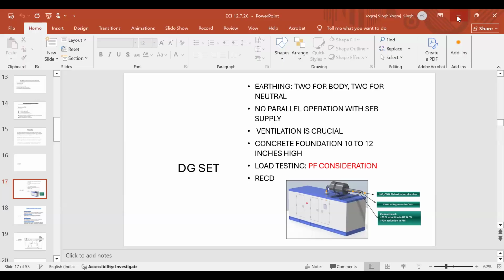Now you have installed a DG set. A DG set can be single, or can be two pieces depending upon the requirement. But you should never run it in parallel with the SEB supply. If there are two DG sets, they will run in parallel with each other. Suppose the load in the system is 1000 kVA and you run two DG sets of 500 kVA. They can be made to run in parallel, but definitely not with one side on SEB supply and one side on DG set supply, because then there is a frequency mismatch. It can create havoc.